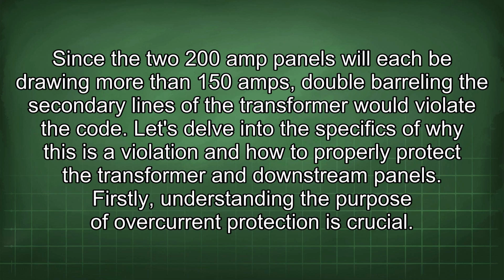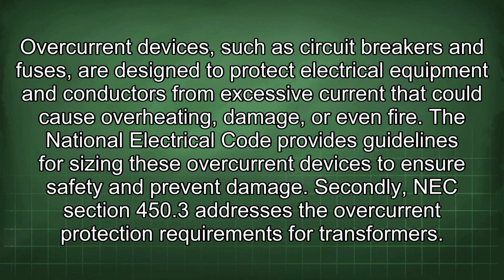Since the two 200-amp panels will each be drawing more than 150 amps, double-barreling the secondary lines of the transformer would violate the code. Let's delve into the specifics of why this is a violation and how to properly protect the transformer and downstream panels. Firstly, understanding the purpose of overcurrent protection is crucial. Overcurrent devices, such as circuit breakers and fuses, are designed to protect electrical equipment and conductors from excessive current that could cause overheating, damage, or even fire.